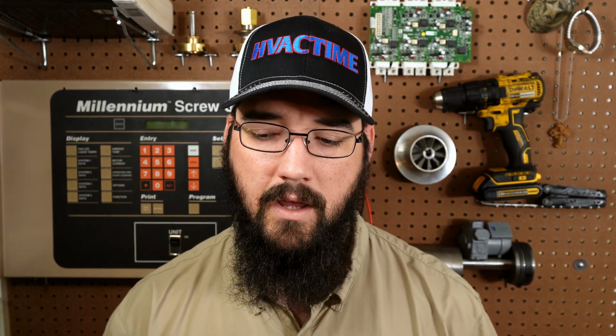For me, usually if I'm working on a system, some of the service manuals may give me a value that those 2 points are supposed to read. But if I'm working in a system, a lot of times there'll be at least 3, because everything's typically 3-phase for me. So there'll be at least 3 in there. And usually I can check across all 3 and then compare the numbers and see which one is just dramatically not even in the ballpark. So then I can address that one that was the standout, if you will.